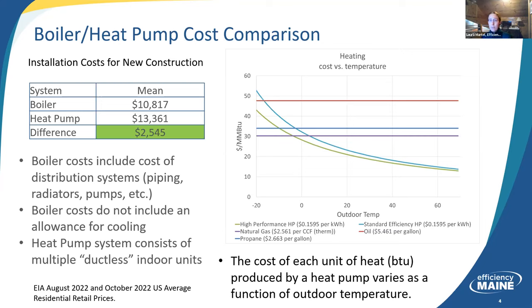And the chart on the right is showing the operational costs of heat pumps versus a high performance heat pump. The high performance heat pump is the green line. The blue line is a standard efficiency heat pump. And I'm using national average costs here. So the cost of electricity is just under 16 cents per kWh. The purple line is natural gas based on $2.56 per therm. So that would be like a natural gas boiler or furnace. Oil is the red line at the top there at $5.46 a gallon, and propane is the blue line in the middle at $2.66. So you'll notice that the natural gas, oil, and propane are flat lines. They're horizontal because it doesn't matter what the outdoor temperature is, every BTU that gets produced costs the same amount based on the fuel costs.